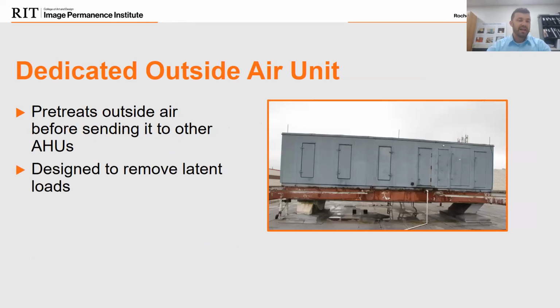One of the last types of units is just a dedicated outside air unit. It is never really a typical or standard type of unit, but the purpose of this unit is to pre-treat any outside air before going to the other unit. So some of the conditions we discussed earlier, the heat and moisture loads of hot, moist air in the summer and cool, dry air in the winter, put a load on an air handling unit, and the units have to compensate for that. Some institutions have dedicated outside air units, and that unit is going to treat the bulk of the outside air coming in before it sends that air onto the other units to use. So if it's a hot, damp summer, that unit will remove that moisture, remove that heat, and then pass along usable air to the other units, so it's less work that they have to do. And again, these are also more energy efficient methods being recommended.